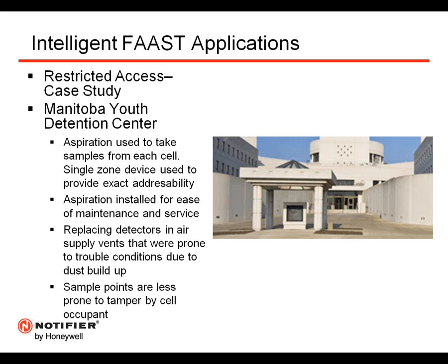The sample points are also less likely to be tampered with by the cell occupant. There are tamper-proof sampling points available, and the sampling points are much more discreet than, say, a spot-type smoke detector, which is going to sit off of the wall and have electronics in it. This sample point is just a hole in a pipe, and using capillary kits, you have a very discreet sample point. And if that sample point is in some way tampered with, if they either clog it up or the pipe breaks, you will get a high or low flow fault at that FAAST detector, signifying that you do need to go out and address the issue.